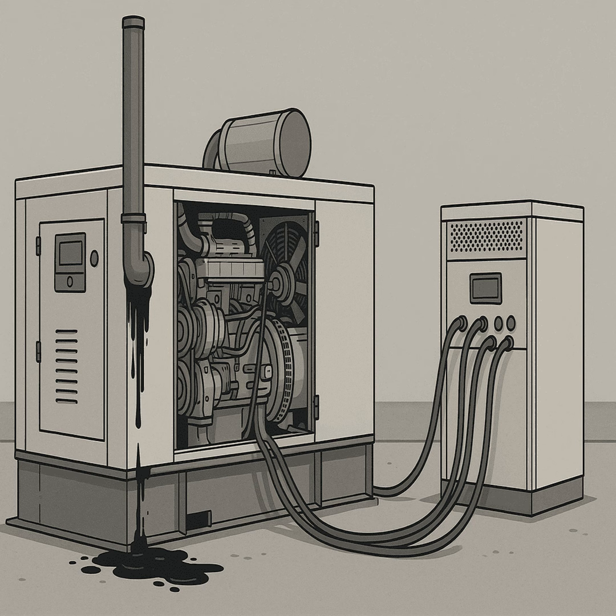Exactly. Consistent load management, whether through actual use or proactive load banking, combined with sticking to the recommended maintenance schedule, using good fuel, and ensuring the generator was correctly sized in the first place—that's your best defense. A well-maintained, properly loaded generator is a happy generator.